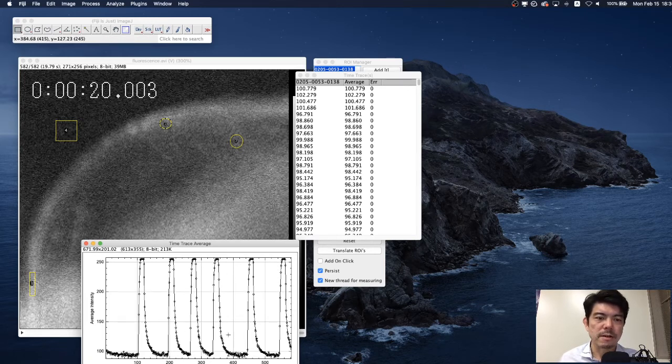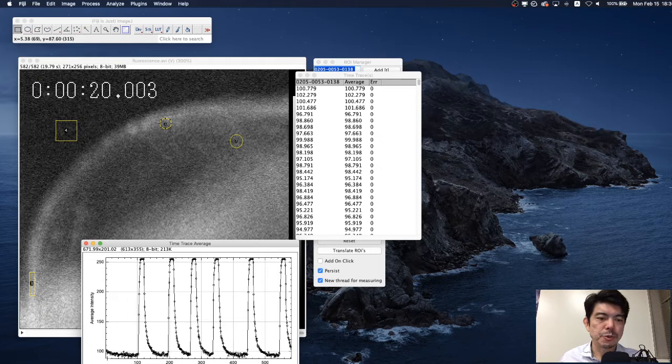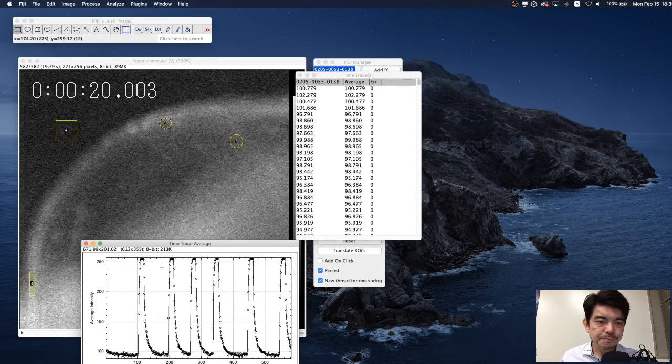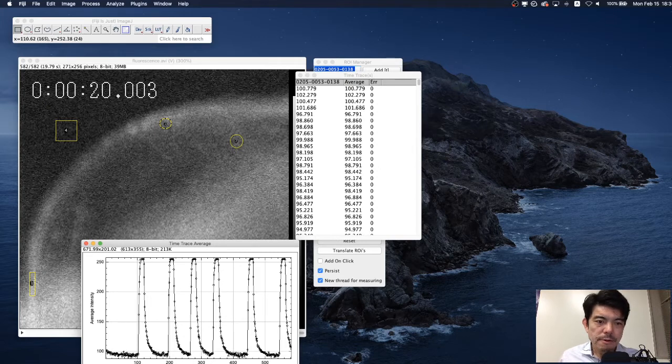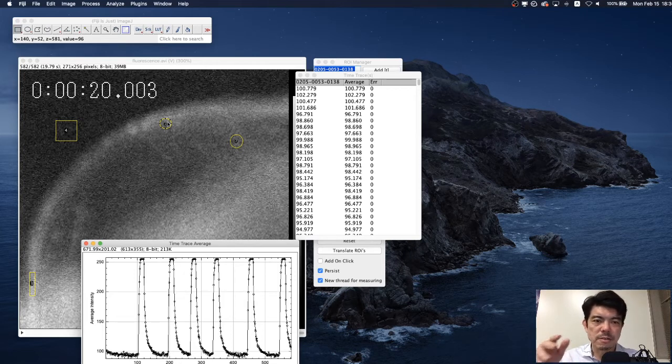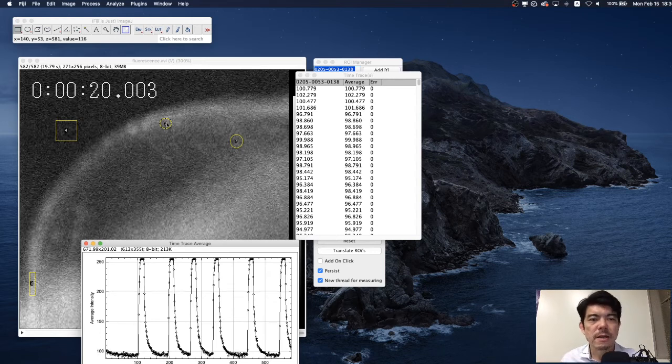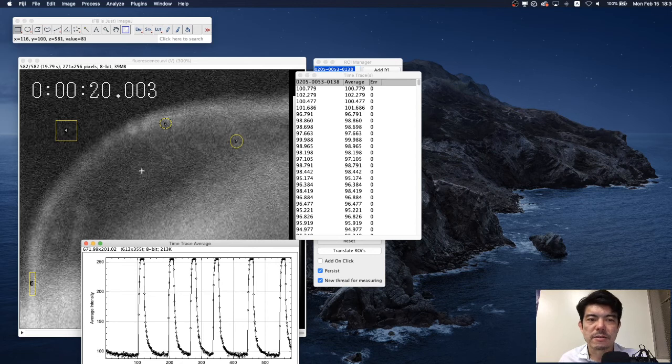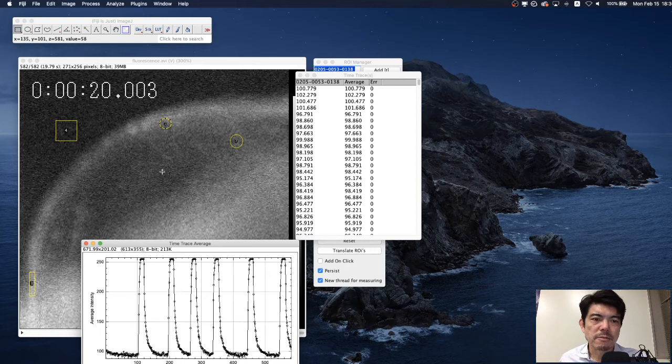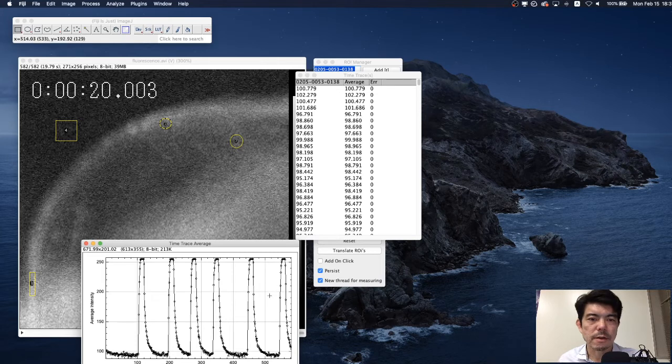Because this is 8-bit image, this signal is between the range between 0 and 255. 255 is the maximum intensity. As you can see here, actually the averaged intensity inside this ROI is 255, meaning that actually the signal is saturated. This is not very good if you want to quantitatively measure the signal intensity. When we record the imaging signal, it's better to reduce gain to have the signal within the range between 0 and 255.